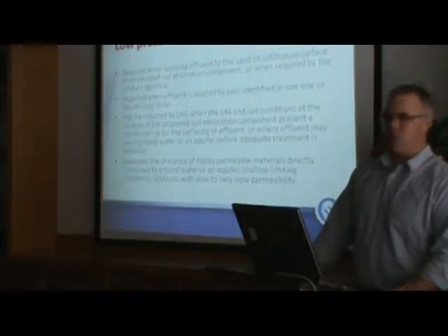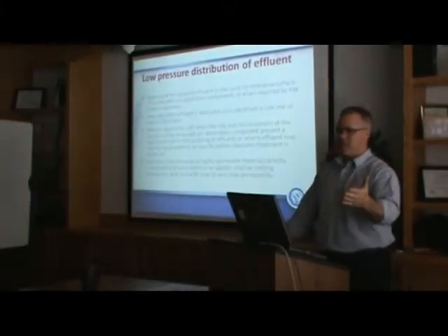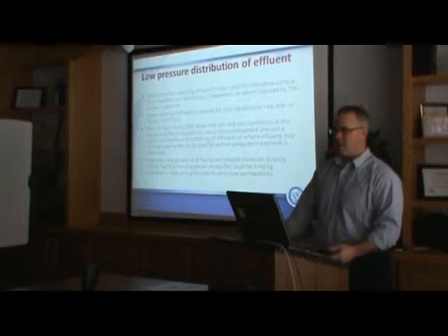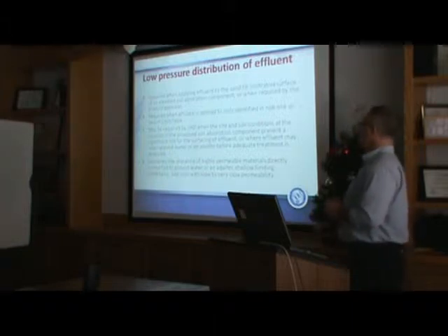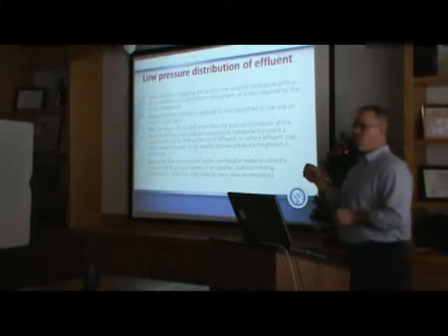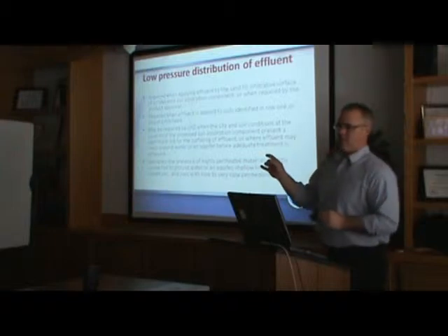When is it required to apply effluent with low pressure distribution? Number one, it's required when you have a sand fill, mounds, sand filters, at least the one type of sand filter. That's when it's required to have low pressure distribution. Number two, soils in the top 1 or 2 rows of the Tyler table.